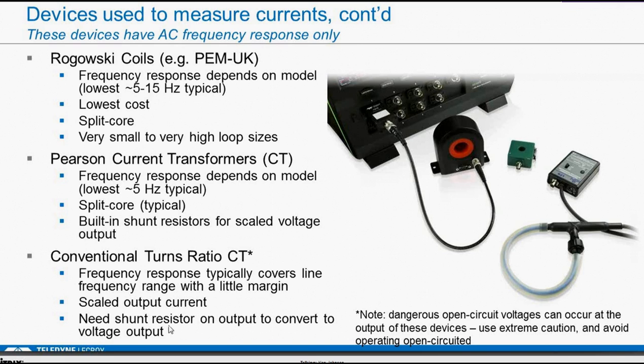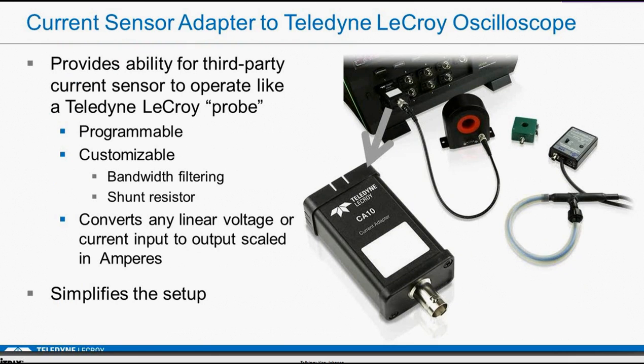You do need a shunt resistor on those on the output to convert to a voltage output to be able to measure in some measurement devices. You have to be careful. Dangerous open circuit voltages can occur at the output of a device if it's open circuited and there's a large amount of current flowing through it. So you do have to be careful in using some of these devices.